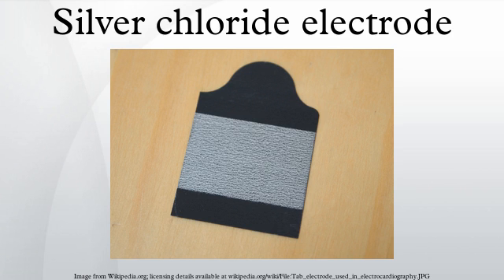Silver-silver chloride is a popular choice for biological electrodes due to its low half-cell potential of approximately 220 mV and the lower impedance of the electrode provided by silver chloride. When appropriately constructed, the silver chloride electrode can be used up to 300 degrees Celsius. The standard potential of the silver chloride electrode as a function of temperature is given by: EO (V) = 0.23695 − 4.8564×10⁻⁴T − 3.4205×10⁻⁶T² − 5.869×10⁻⁹T³.